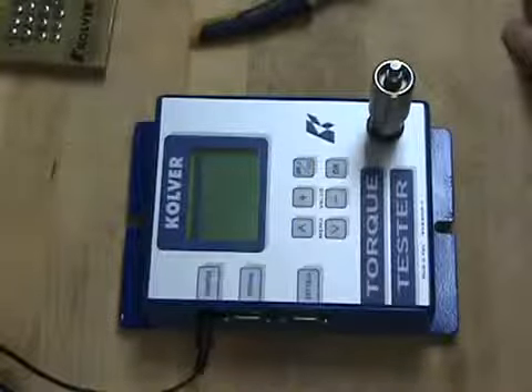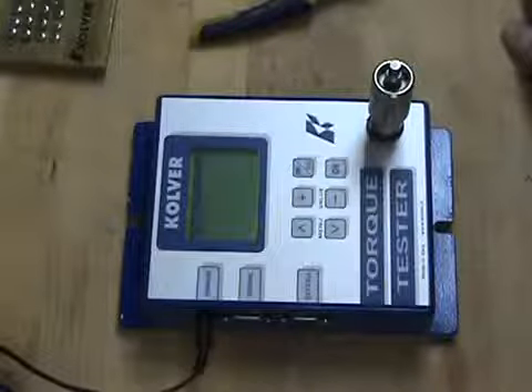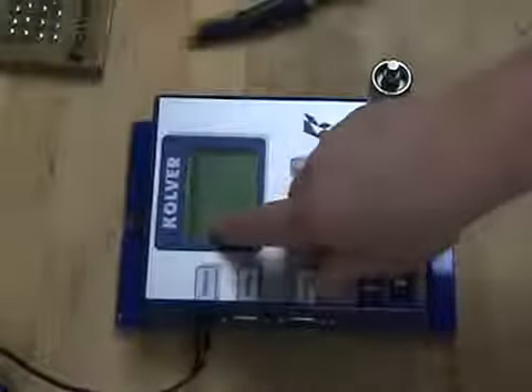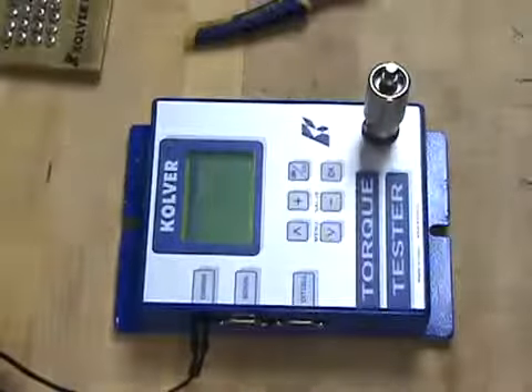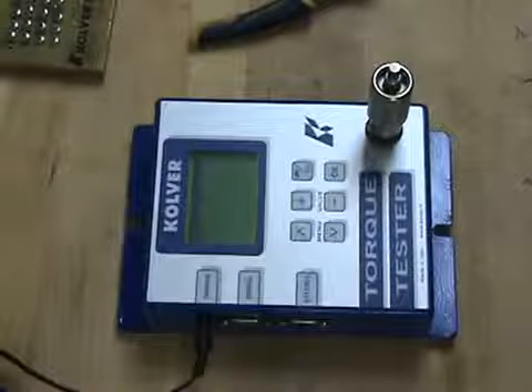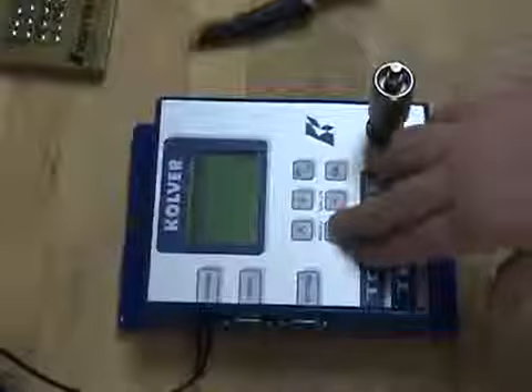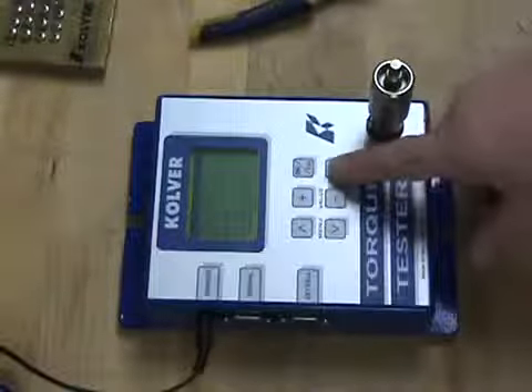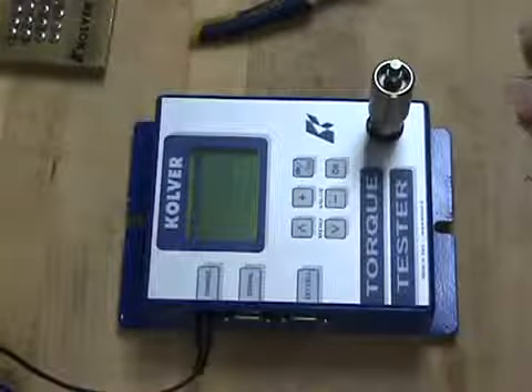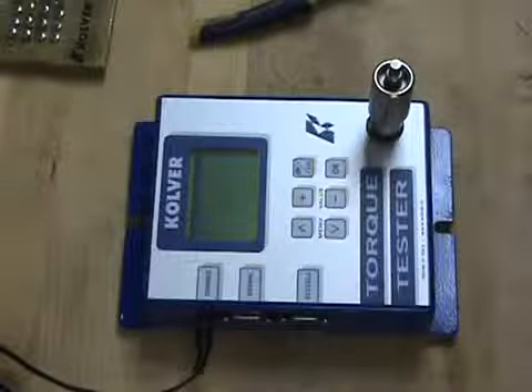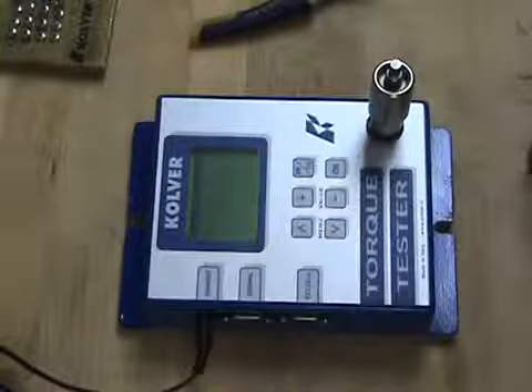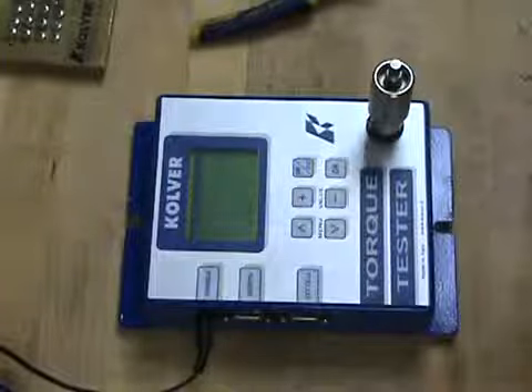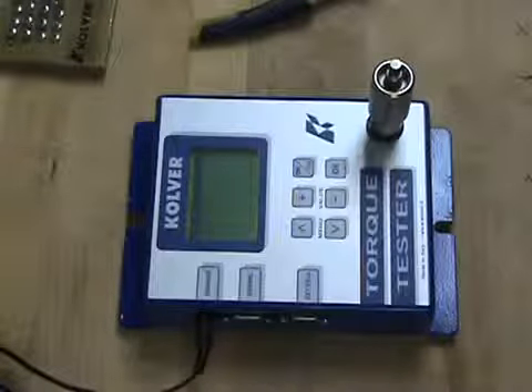The RS-232, there's not much you can do to this one. It's just telling you the 9600 baud and all the other connection details. You will not have the opportunity to change those. Calibration, this is something that will be done in a Cal lab, so we're not going to be going over that. And you can select internal or external transducers. The external, of course, is for the external cell that you would plug in here.